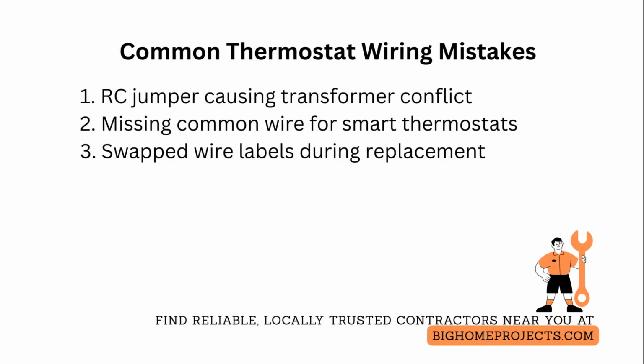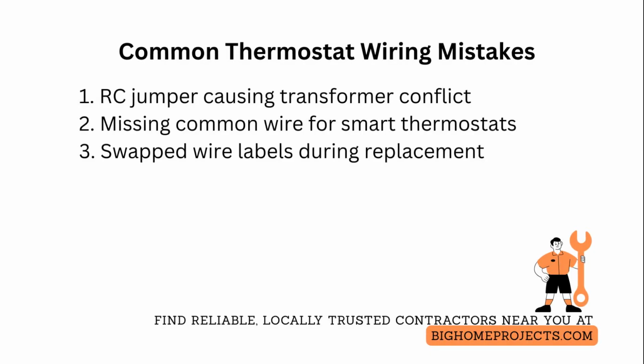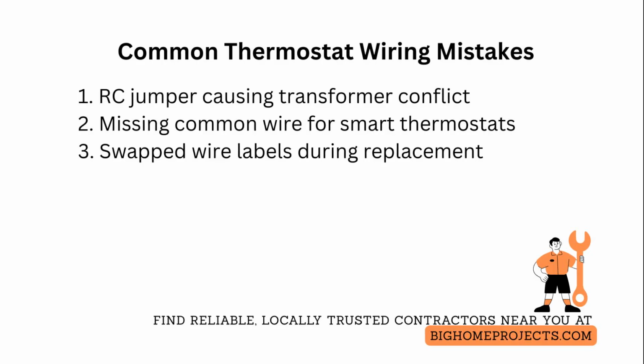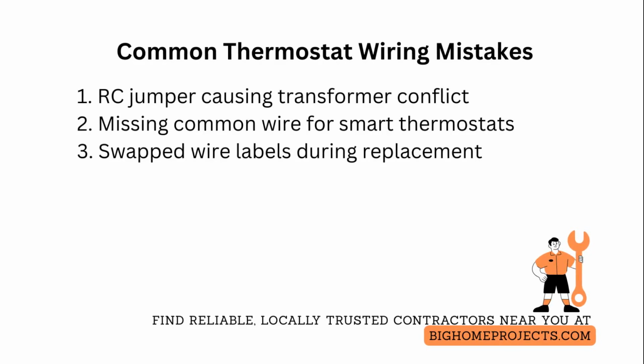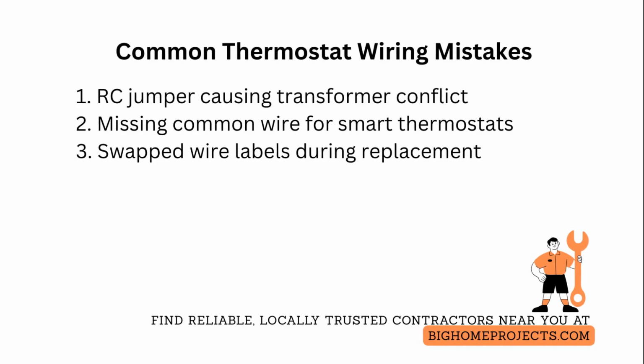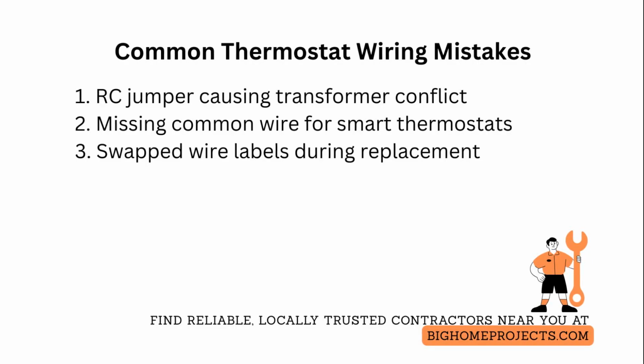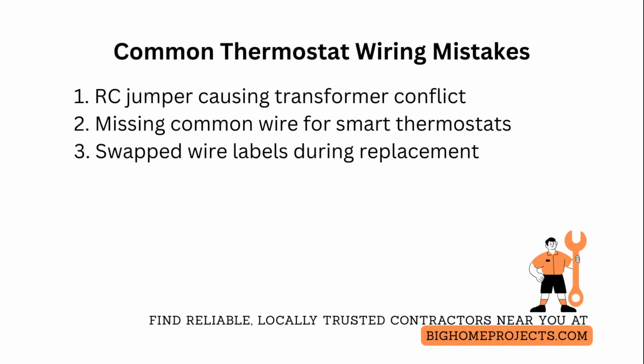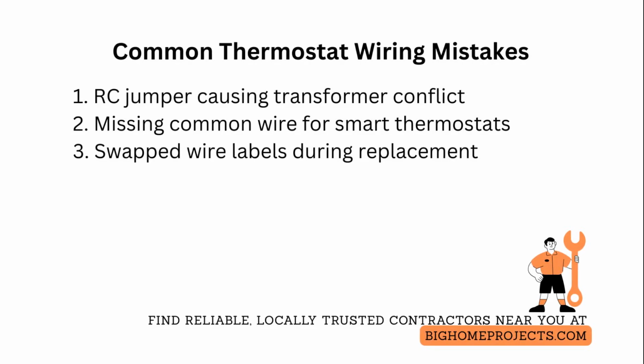One of the biggest mistakes homeowners make is misplacing the RC jumper, causing transformer conflict and blown fuses. Fix this by identifying whether you have one or two transformers and keep the jumper only for a single transformer system. The second common issue is assuming every smart thermostat needs a common wire, which leads to dead displays. Fix this by testing for a C conductor at the stat location or installing a power extender kit from the thermostat maker.